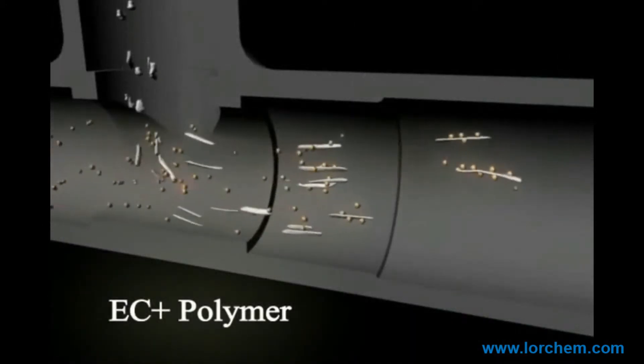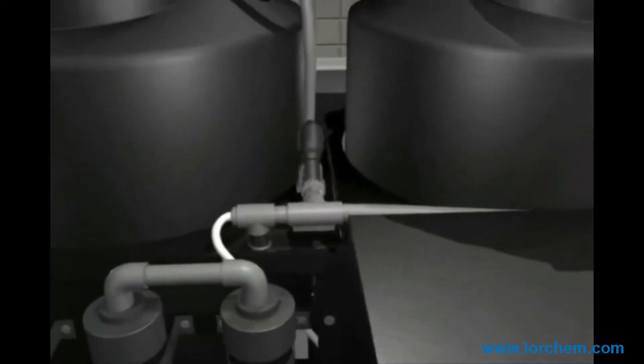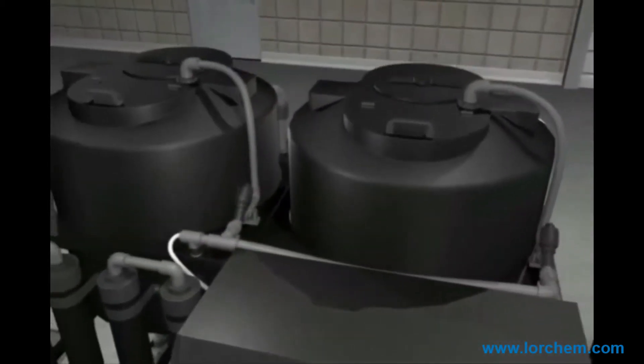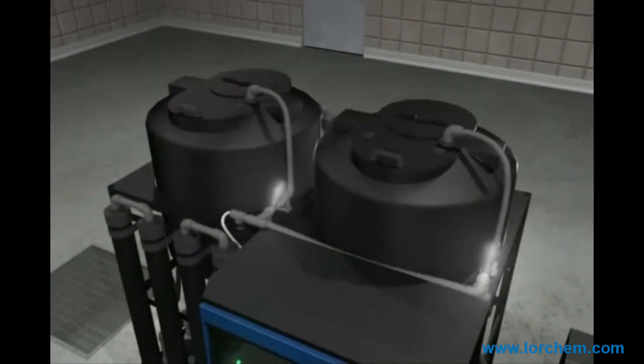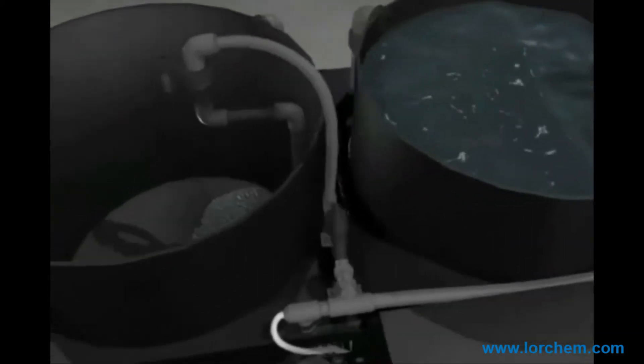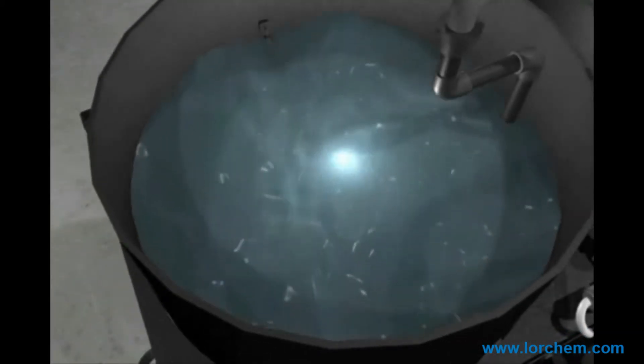The COAG system's PLC directs the treated water into one of two integrated cone bottom settling tanks. An automatic valve directs the flow for uninterrupted operation at up to 20 gallons per minute. The chemical reaction continues within the tanks and the solids quickly fall, where they are collected in the cone bottom portion of the tanks.